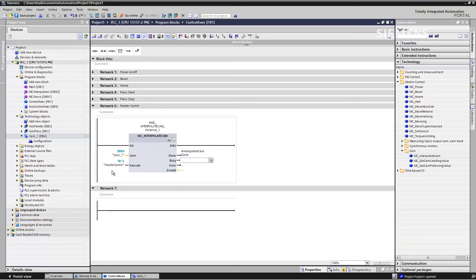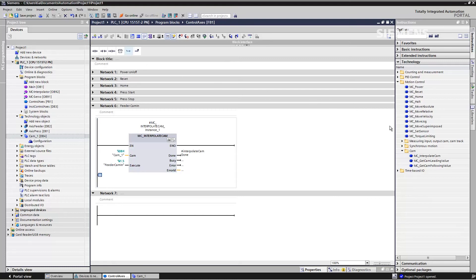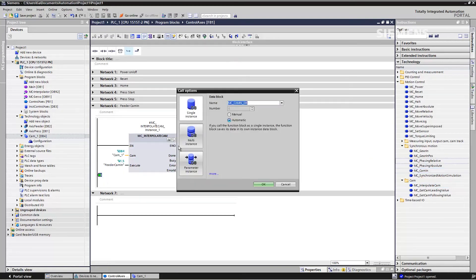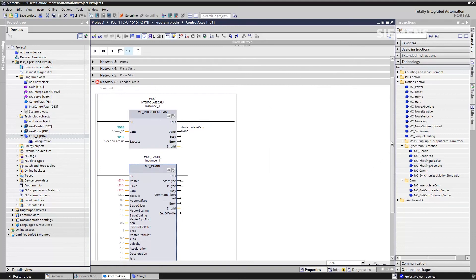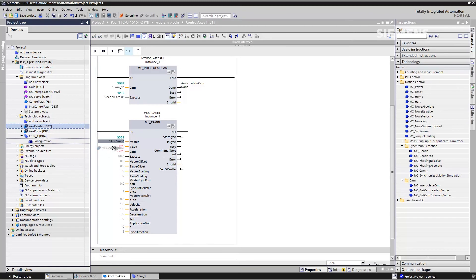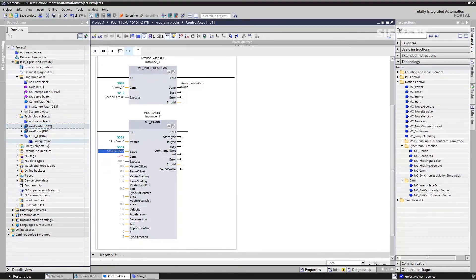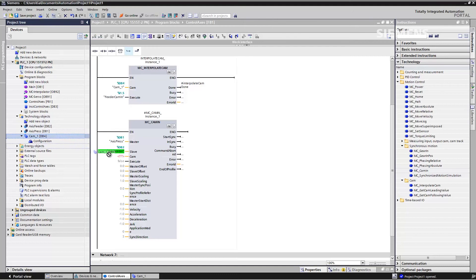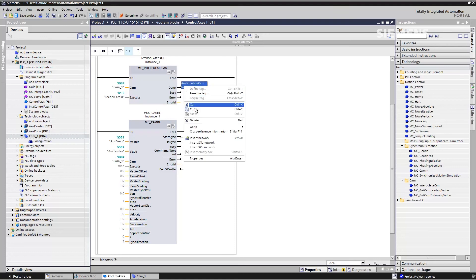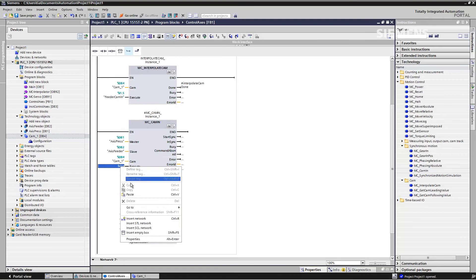As soon as the interpolation has been acknowledged with done, we proceed to the actual coupling using the function CamIn, and we couple the infeed axis to the press axis. This means simply dragging the press as the master axis and the infeed as the slave axis, so both axes move in a coupled manner through the positional relationship we've just defined. The whole procedure should be launched as soon as the CAM disk is available. There are also options to adopt, move, and scale the CAM disk.